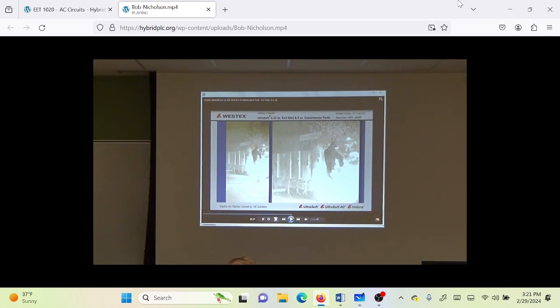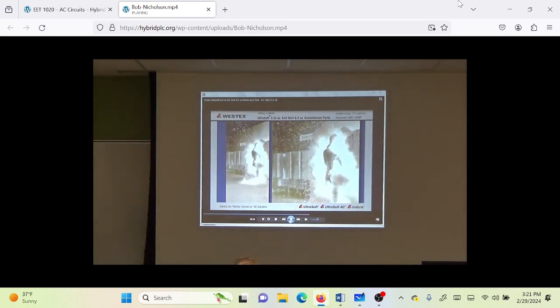This is not a steel mill. This is a person now. It's primarily a lower body event. That's copper and steel flying. An enormous amount of molten metal is being thrown up in the air. It's going to land 20, 30, 40 feet away. What you don't want to do is approach anybody when those panels are open, because if you don't have the protective clothing on, you're going to get it.